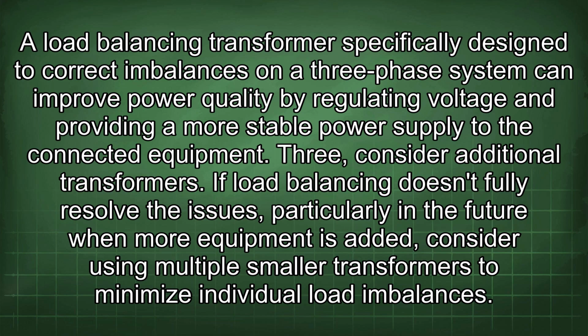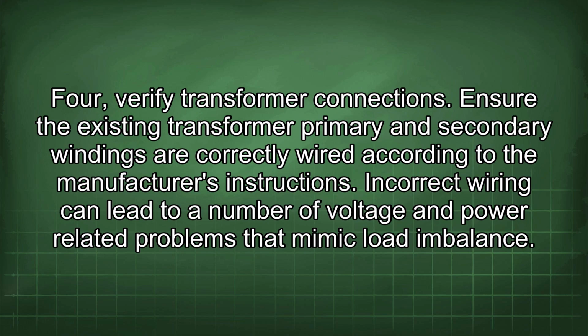3. Consider additional transformers. If load balancing doesn't fully resolve the issues, particularly in the future when more equipment is added, consider using multiple smaller transformers to minimize individual load imbalances. 4. Verify transformer connections. Ensure the existing transformer primary and secondary windings are correctly wired according to the manufacturer's instructions. Incorrect wiring can lead to a number of voltage and power-related problems that mimic load imbalance.